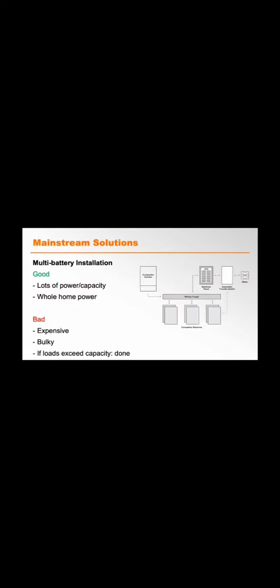So for PWRcell, because we are bigger and have more capacity and more power, running just the essentials looks pretty good. It's not bad. And you might actually be able to keep on some of the larger essentials. Your well pump, that kind of thing, could reasonably be on the protected loads panel. But what about all that other stuff in your customer's home? How do you tell them that they can't do the laundry or open the garage doors or use the entertainment room during an outage? Tough stuff.